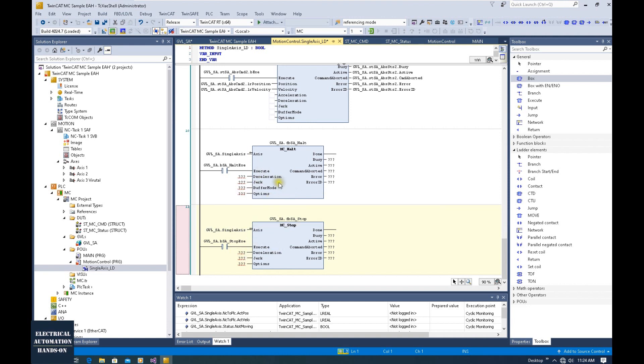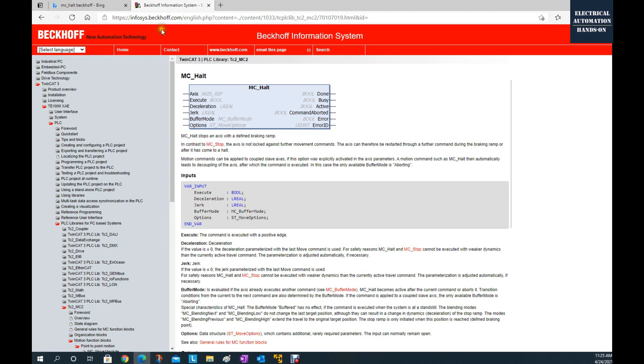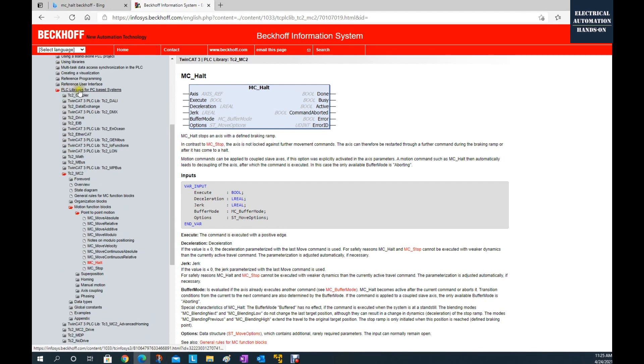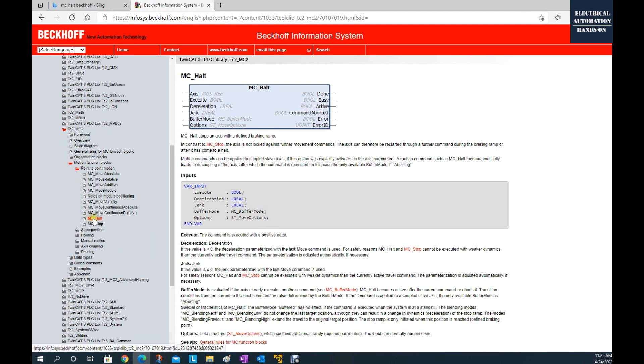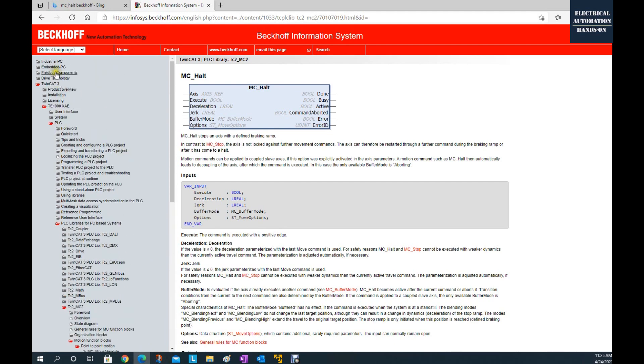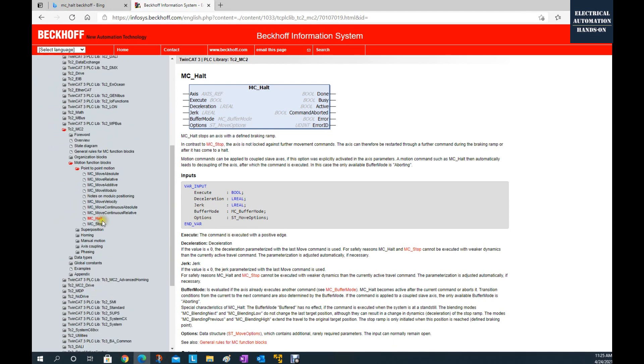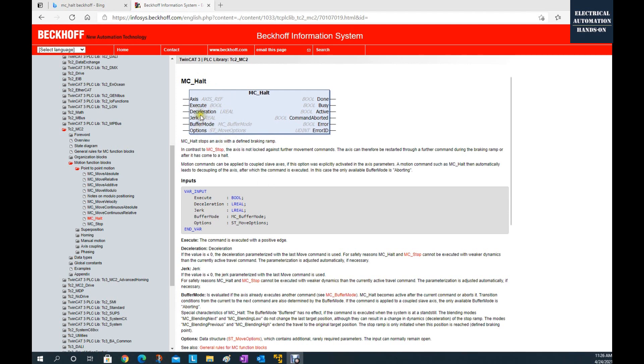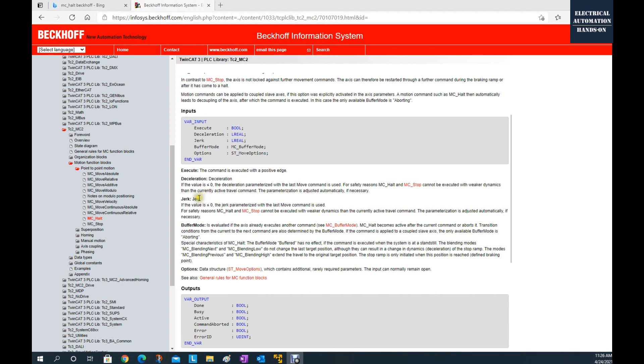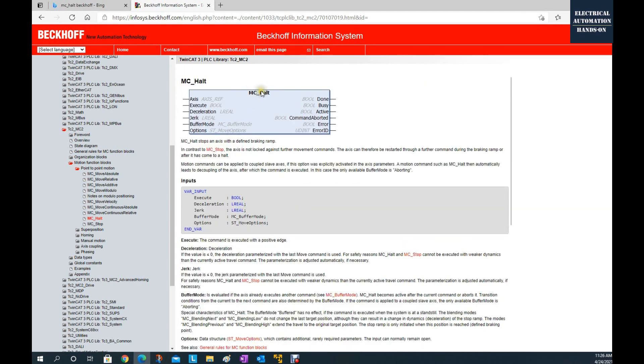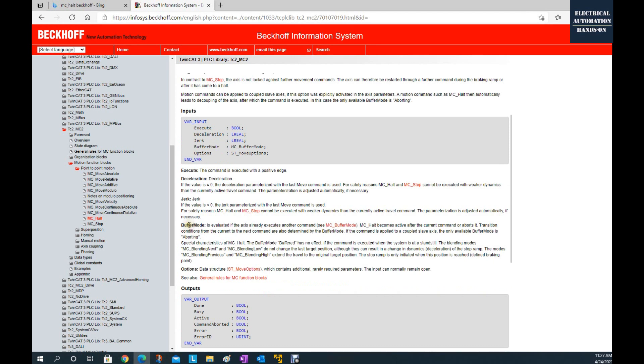For other variables, we can go online and find out the Infosys Beckhoff system. From the Infosys Beckhoff website, let's find the PLC library for PC-based systems: TC2_MC2, Motion, Function Blocks — and find MC Halt and MC Stop. For MC Halt, take care of two things: the execute command and the buffer mode. For the execute, take care — this command is executed with a positive rising edge. That means this function block will be executed by rising edge only. Also, note the buffer mode — this allows MC Halt to stop the axis in different ways.